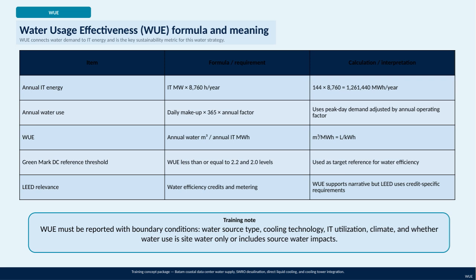To put this into context, the Green Mark data center reference sets thresholds for WUE at 2.2 and 2.0 levels, serving as target benchmarks for water efficiency. Meanwhile, LEED certification considers water efficiency credits and metering, where WUE can support the narrative, although LEED requirements often focus on specific credit criteria. One important training note is that when reporting WUE, it's essential to specify boundary conditions. This includes factors like the type of water source, the cooling technology employed, IT utilization rates, local climate conditions, and whether the water use accounts only for site water or if it includes broader source water impacts. By doing so, we ensure transparency and comparability in water efficiency reporting. In all, understanding and applying WUE helps us optimize water use, improve sustainability, and meet industry benchmarks for efficient data center operation.